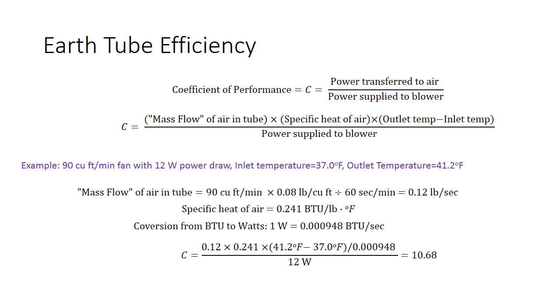Specific heat of air, you can look this up online, is 0.241 BTUs per pound degree Fahrenheit. We're going to want to convert from BTUs to watts. The conversion factor, a watt is a unit of energy or heat per unit time. That conversion factor is 0.000948 BTUs per second equals one watt.